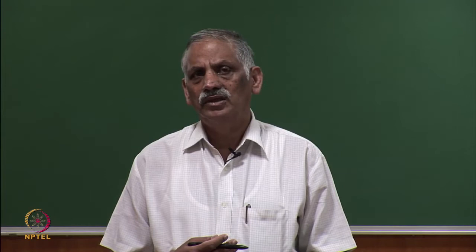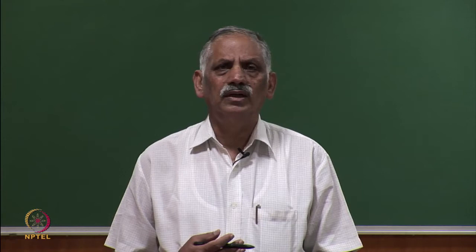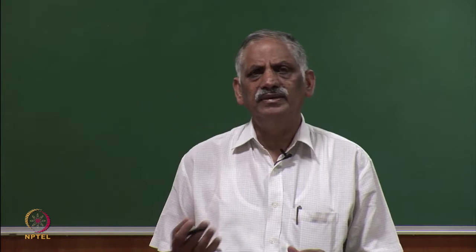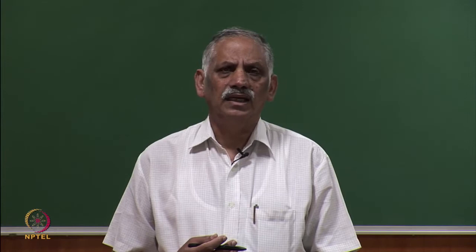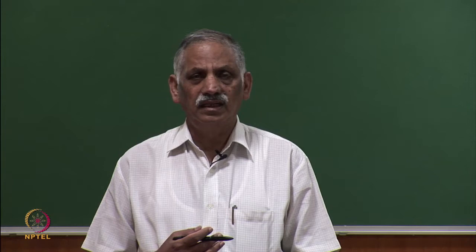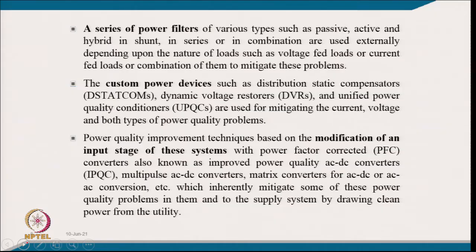Similarly, for series compensation we have the Dynamic Voltage Restorer — DVR — which regulates the voltage across the load even when the supply voltage has sag, swell, unbalance, or harmonic distortion. By injecting a compensating voltage in series with the line, the load experiences ideal balanced sinusoidal supply. The Unified Power Quality Conditioner — UPQC — mitigates both current and voltage power quality problems simultaneously.